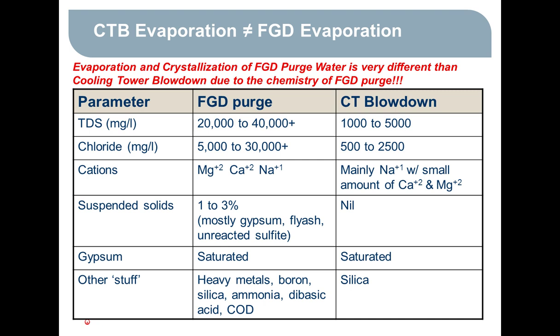The thing to understand about FGD purge is that it's very, very different from cooling tower blowdown. It's a lot more concentrated. It's got a lot more chloride, so it's very corrosive. It's got a different set of cations. It's mostly calcium and magnesium base as opposed to sodium base for cooling tower blowdown. Lots of suspended solids in it. It's saturated in gypsum because that's the byproduct that's made in the scrubber. And it's also got a lot of other things in it, like heavy metals, boron, silica, selenium, dibasic acid, sometimes COD, who knows. There's a lot of different things that can be involved in FGD purge water.